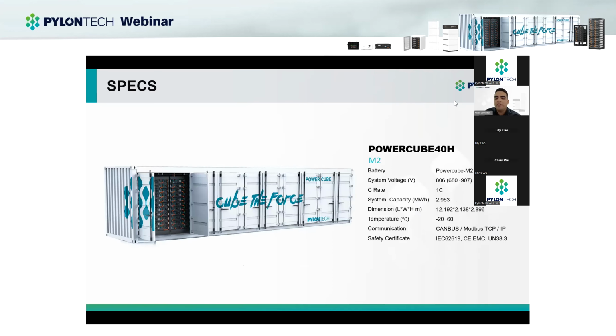Also, we have the 40 feet container with the M2 battery, where the voltage will be similar, from 680 to maybe around 900. It can also be 1C for 1 hour, but in this case it's double, so we have almost 3 megawatt hours, exactly 2.9 megawatt hours for the battery. As you can see, it's maybe the same as the first solution, just double the size.